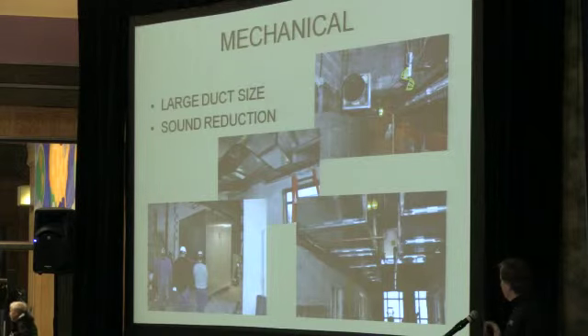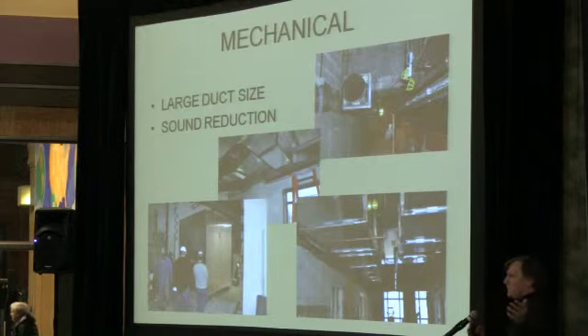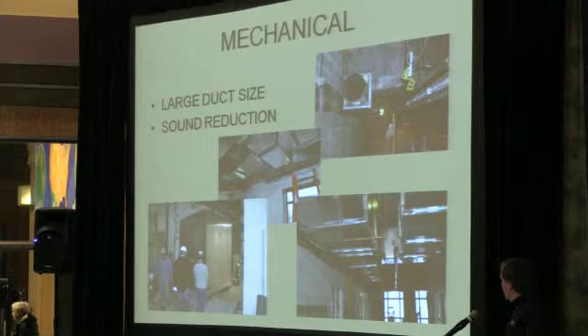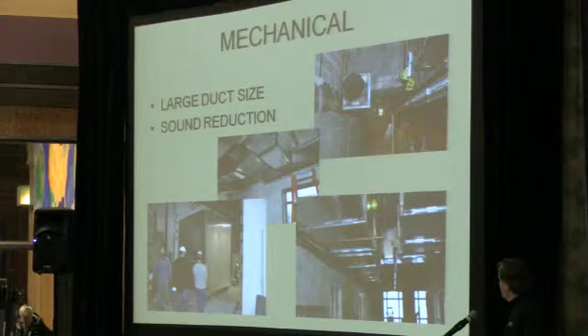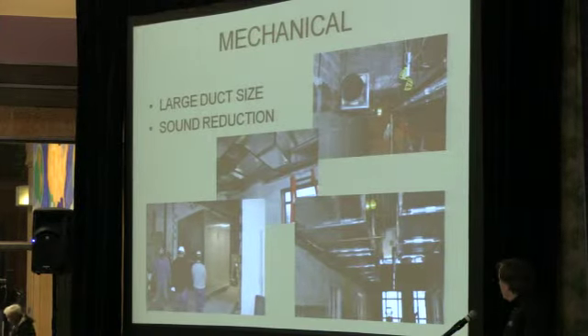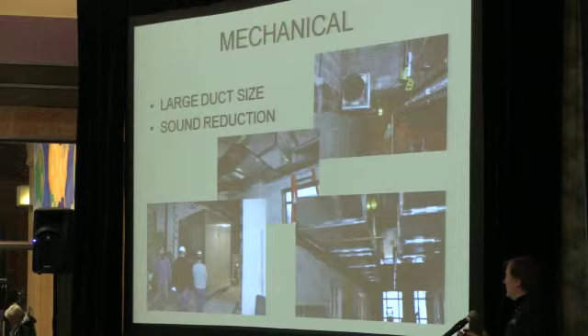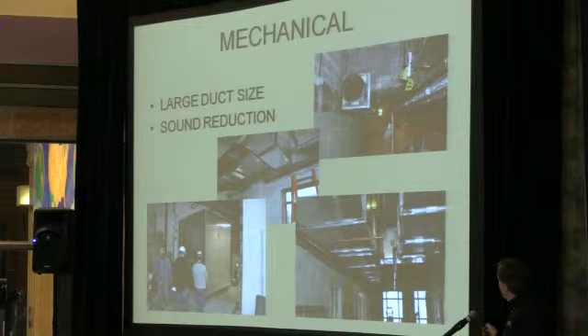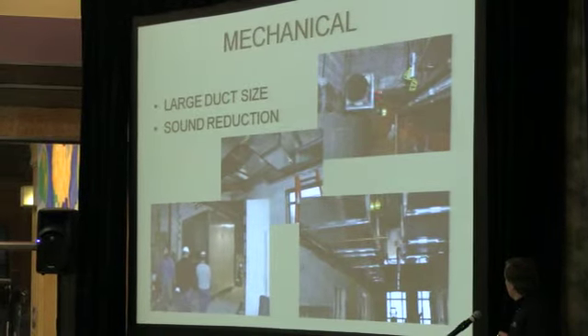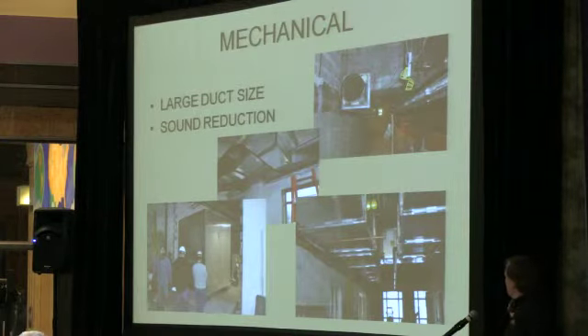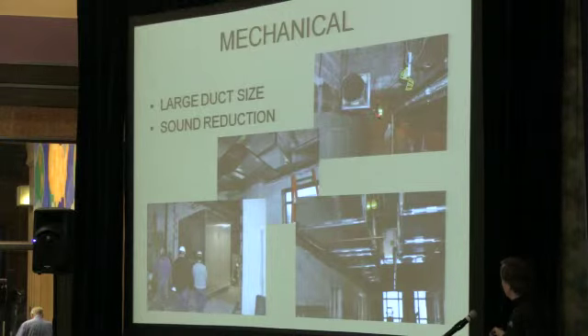It was designed so that the rooms being fed could have little or no sound from the air blowing, which in turn made all the duct sizes a little bit larger than we would normally install. Here's the return above the CDR, and our acoustic plaster was right here. Well, all the beams in the building drop down. There's a lot of void space up there, but we can't run our ductwork up and down all the time, so we're constantly dealing with this parameter of the bottom of the beam to the top of our ceilings.